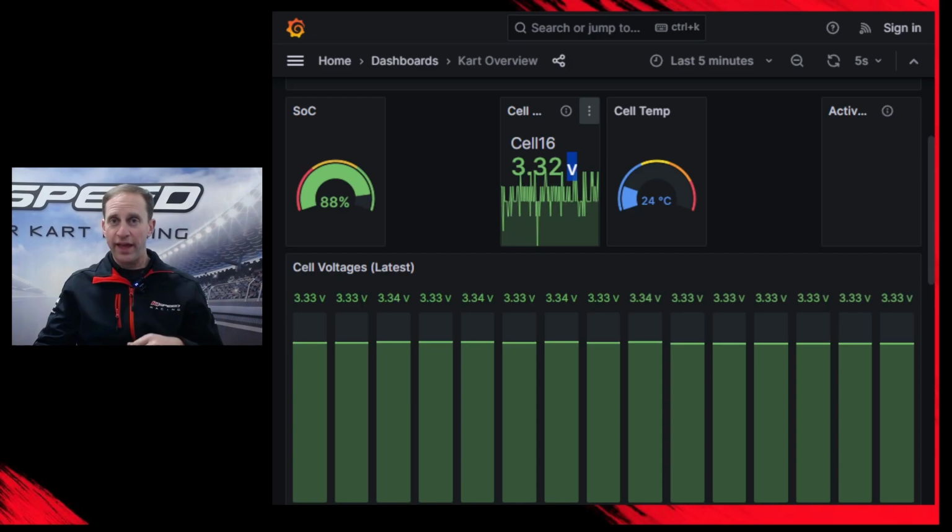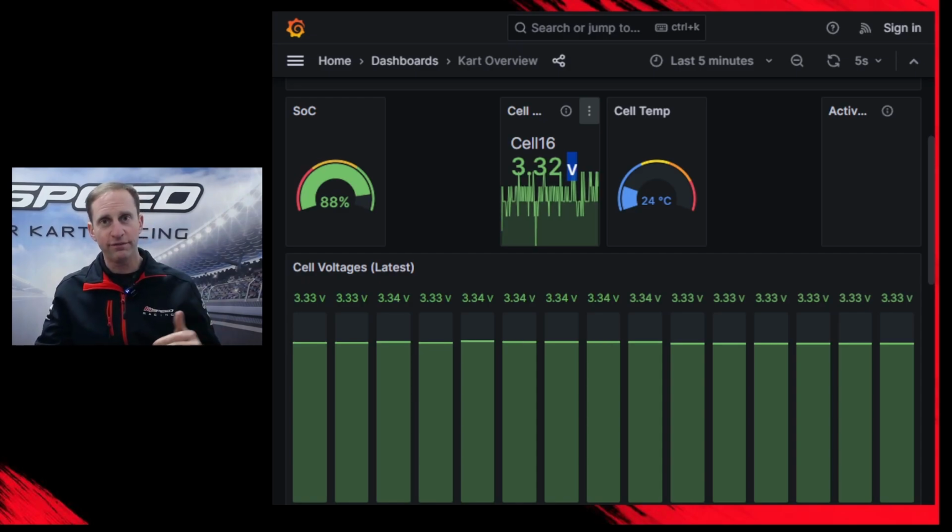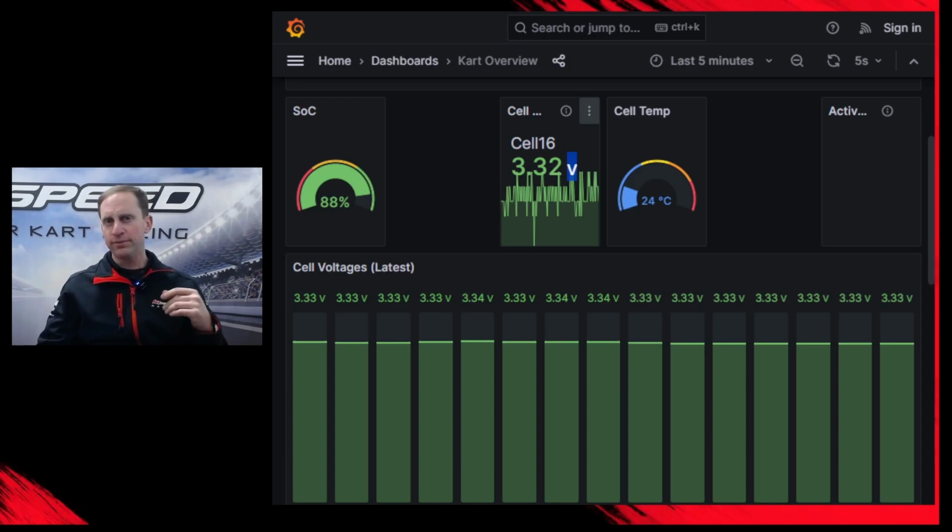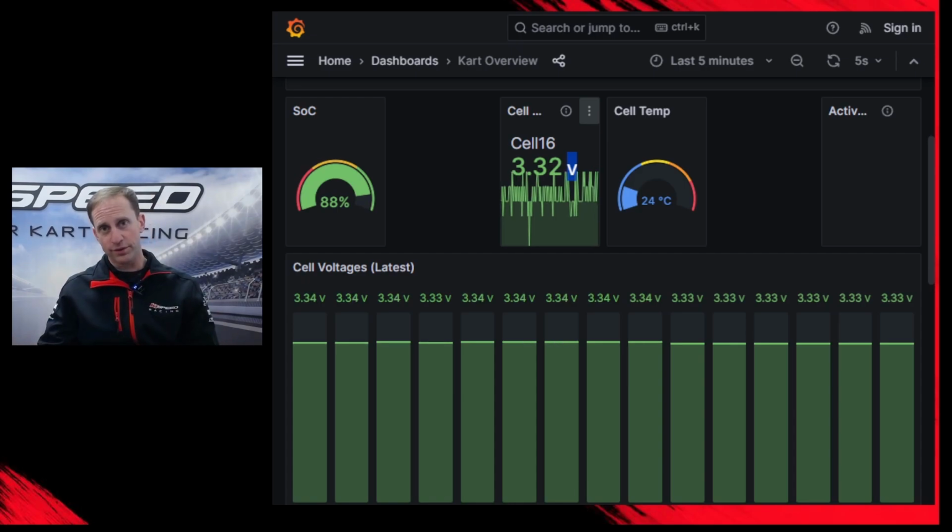This box is going to highlight that for you. And when that lowest cell in the pack reaches 2.5 volts for 2 seconds, the battery will shut off. So that's new this year. If you had telemetry last year, you were probably at 2.2, or maybe some of them were 2 volts. The reason for that was because of a misread or a problem. This value is different this year. You are looking at 2.5 volts for 2 seconds.